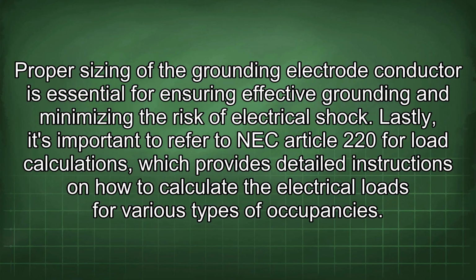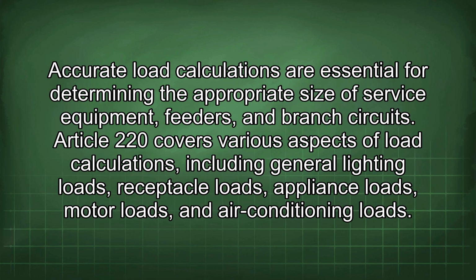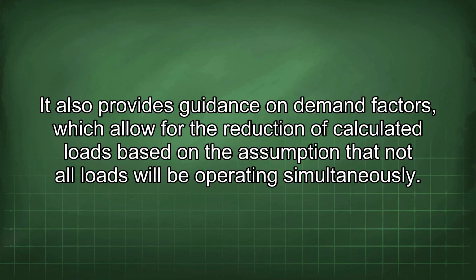Lastly, it's important to refer to NEC Article 220 for load calculations, which provides detailed instructions on how to calculate the electrical loads for various types of occupancies. Accurate load calculations are essential for determining the appropriate size of service equipment, feeders, and branch circuits. Article 220 covers various aspects of load calculations, including general lighting loads, receptacle loads, appliance loads, motor loads, and air conditioning loads. It also provides guidance on demand factors, which allow for the reduction of calculated loads based on the assumption that not all loads will be operating simultaneously.